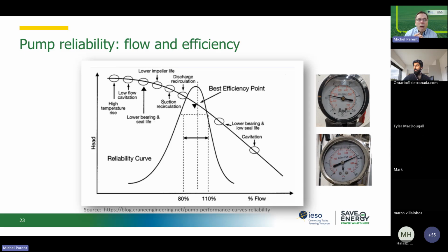If you have directly driven pumps, most pumps are oversized. It is very rare that an engineer will install a pump that is exactly what the system needs. Because if they made any kind of underestimation, they end up with a pump that's too small for whatever service it's supposed to provide. So you should always know that in your building, all your pumps are likely slightly oversized by a safety factor.